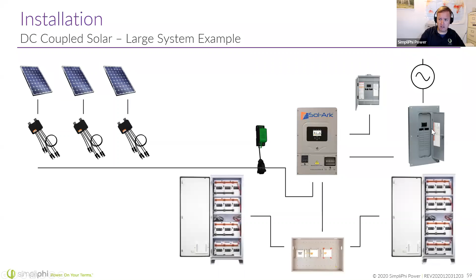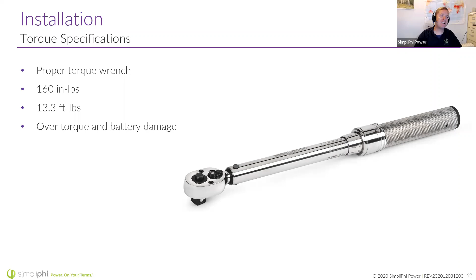I want to see 160 inch-pounds, which is maybe less than what you think it is. The last thing I want to see is you, last day of the job, making up those battery connections, and you get out your impact driver and go to town and one of the battery lugs snaps off. You're dead in the water. Please get your torque wrench. Hopefully it's been recalibrated recently. Maybe it should be insulated, but again, remember, we've turned the battery breaker off. So even if you do short out the battery with this wrench, you're not going to get a big pop.